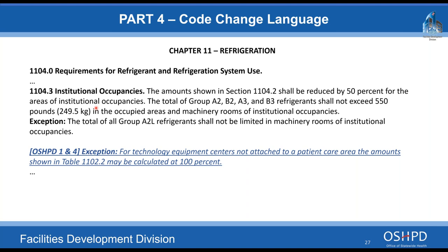are excellent for cooling IT rooms and stuff like this. And we found those were just not being allowed in a lot of instances where they would be perfectly safe. That's all we're trying to do here. We're trying to give the healthcare providers and designers more options on these types of systems. They'll help conserve energy, and there's no reason why they can't be installed in these technology equipment centers not attached to patient care areas. So that's all we're doing there, and we got zero negative input on that in the public comment period, which was really nice. Next slide, please.